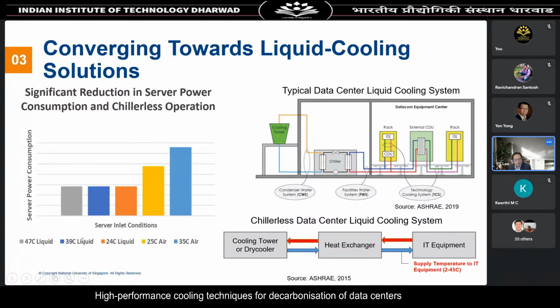But if you look at the figure on your left, it shows that going from 24 to 39 to 47, the server power consumption basically stays flatline. So the implication is you can do away with the chiller, meaning there's no need to use a chiller to condition your inlet temperature. You can allow your inlet temperature to be a few degrees above your outdoor temperature, as illustrated by the figure below. So you can have your liquid cooling directly coupled to the cooling tower or dry cooler, through the use of a heat exchanger, and in doing so, you'll be able to operate chillerless data center liquid cooling systems.